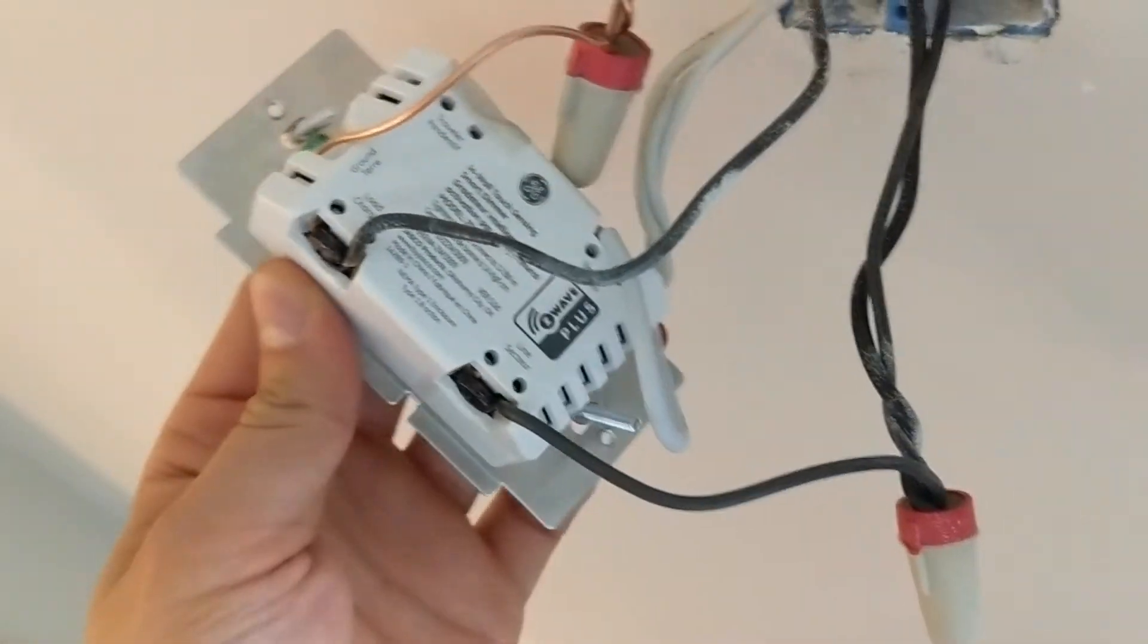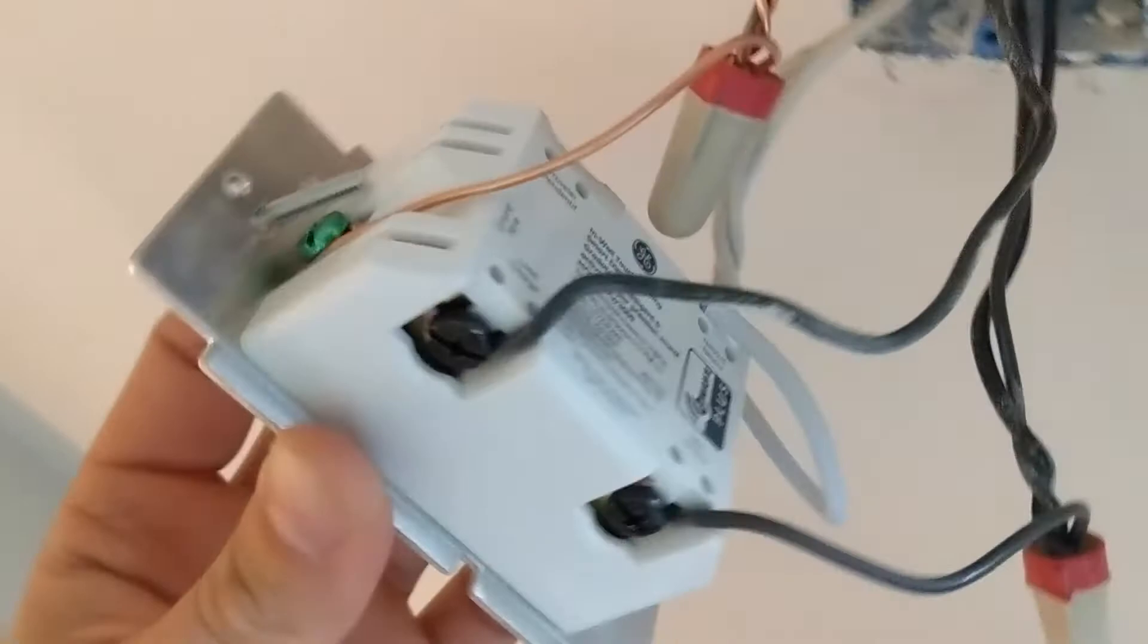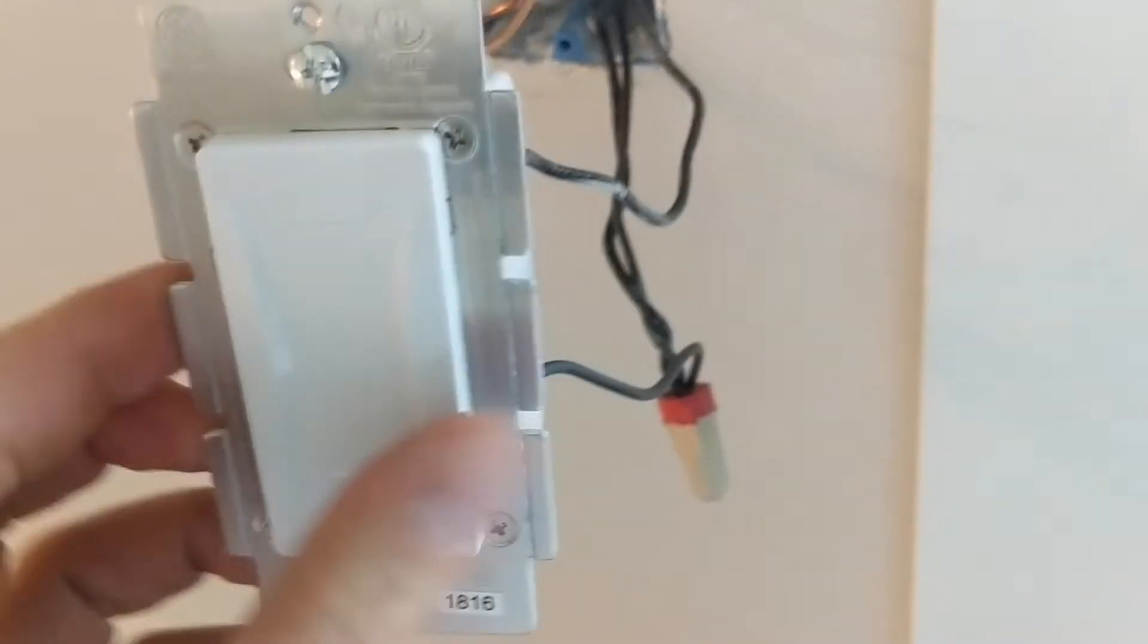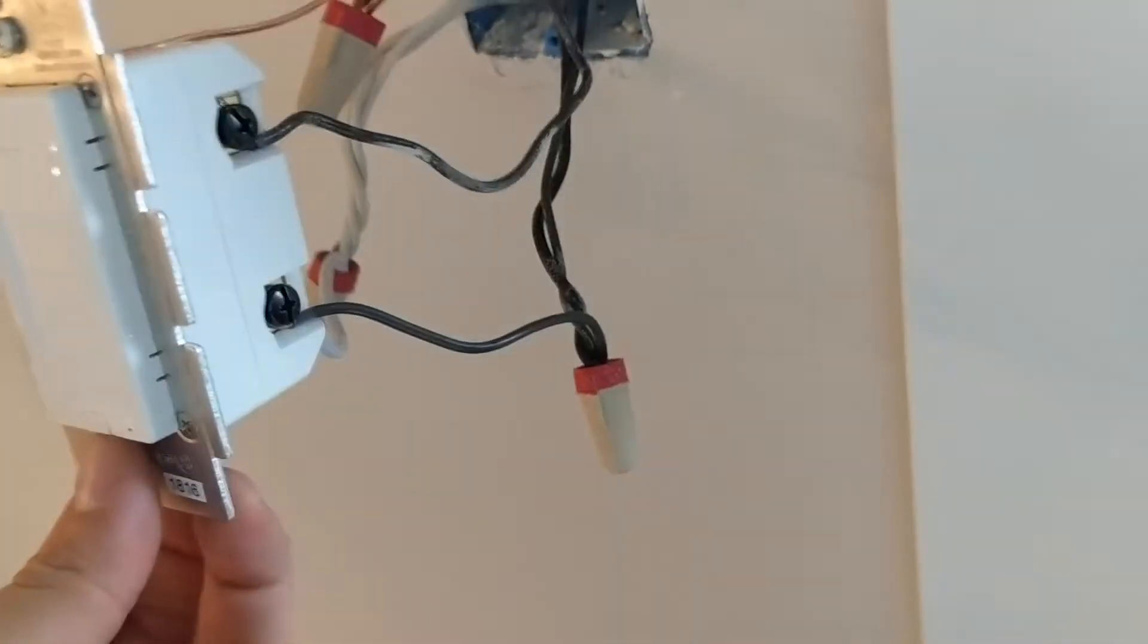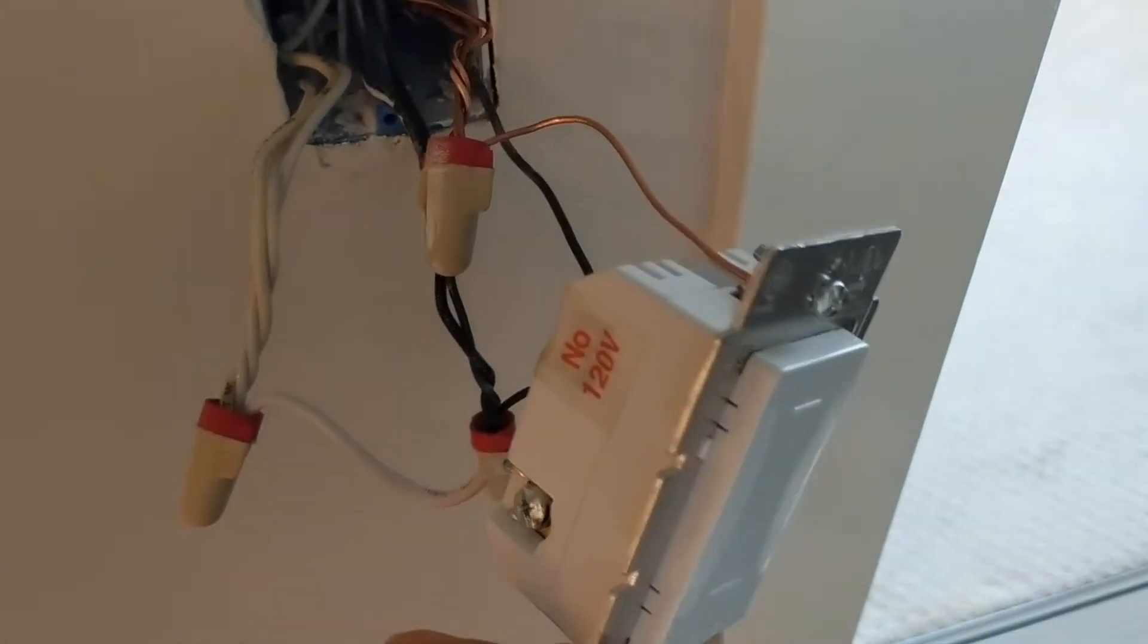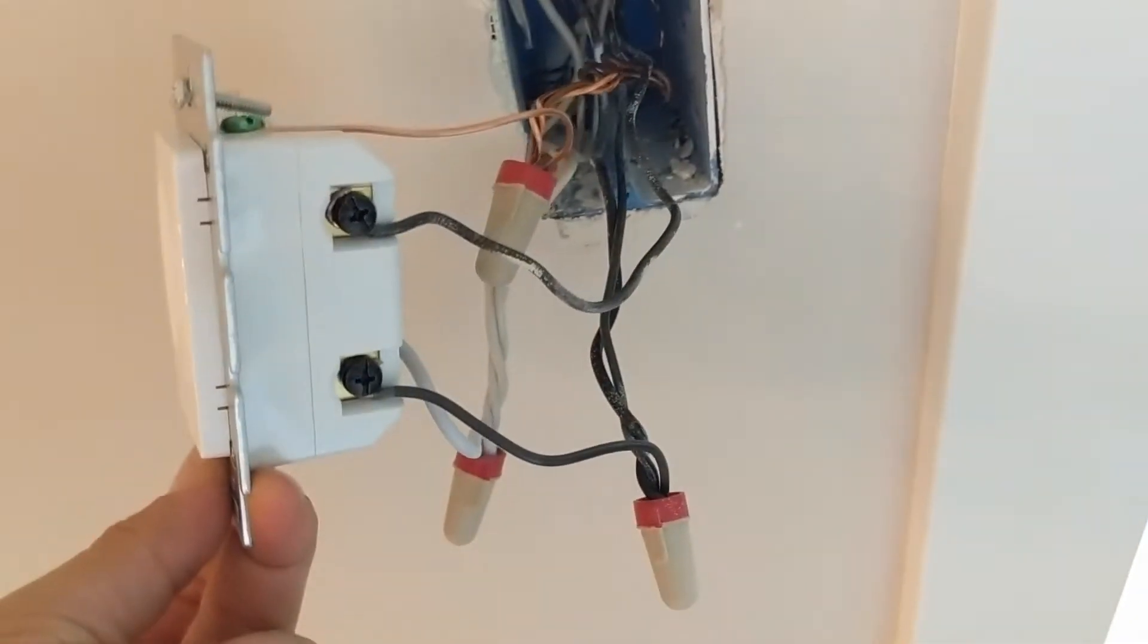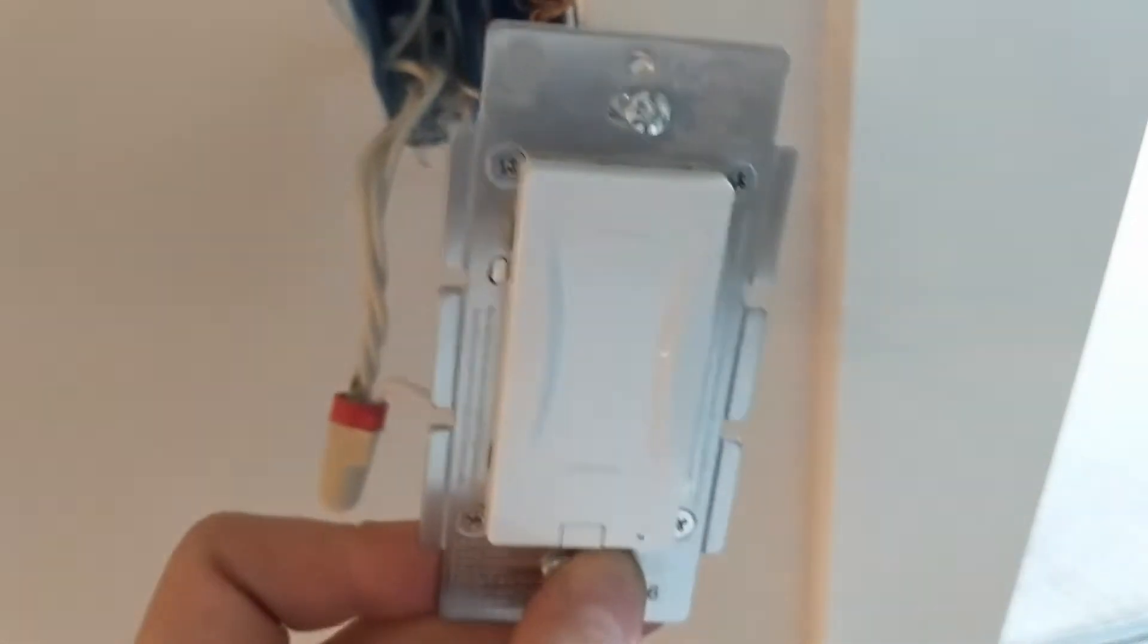The switch does have the quick connects in the back. I'm not a big fan of them, so I don't use them. And make sure that you use 14 gauge wire. 12 gauge wire will not fit on the terminals. Just FYI.